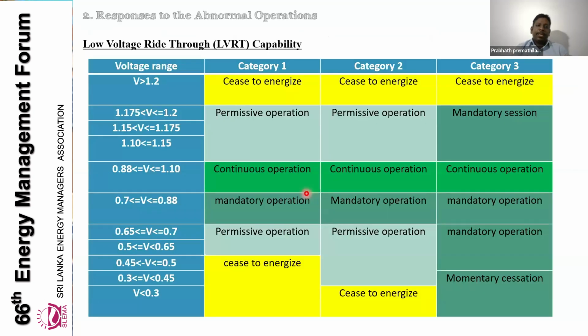Next one, when we have a disturbance in our network, voltage disturbance or frequency disturbance, I explained that so far we wanted to disconnect the solar PV system from the network. But there's an opportunity, a facility, to keep the solar PV system connected and get support out of it. When we talk about these ride-through capabilities in abnormal operations, the inverter will normally go through a few control modes. I highlighted this one in yellow color: the cease to energize mode.